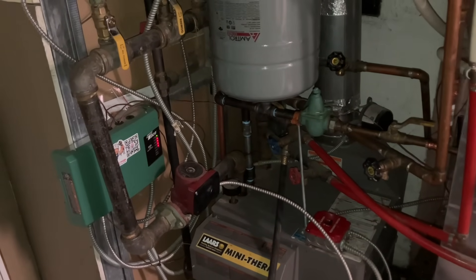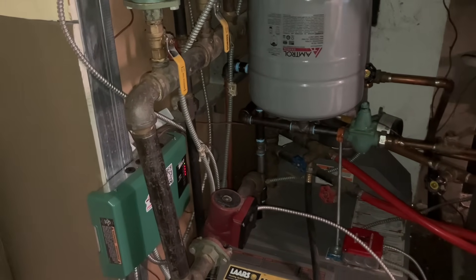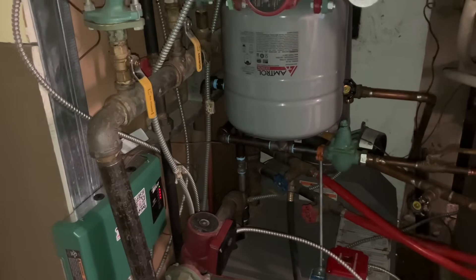I've been here for another hour and a half. I totally overlooked something — no air removal anywhere in the system. Anywhere. The only one I can remotely find is right there on top of the fan coil inside the air handler for the first floor forced air zone.